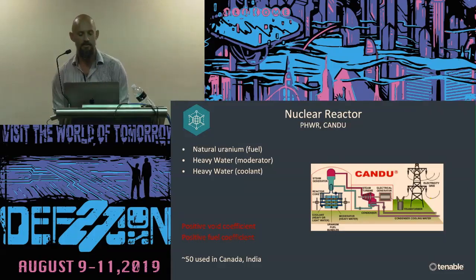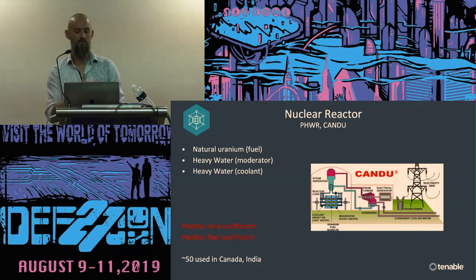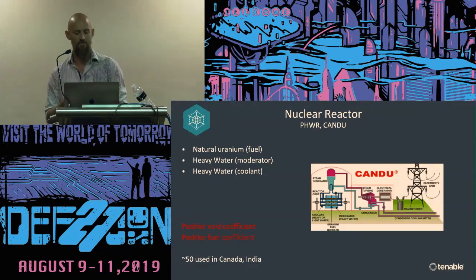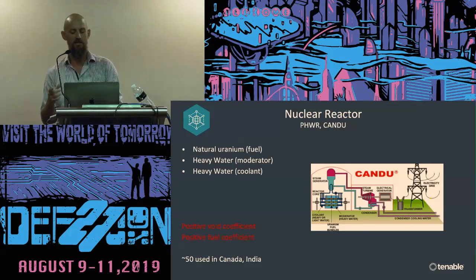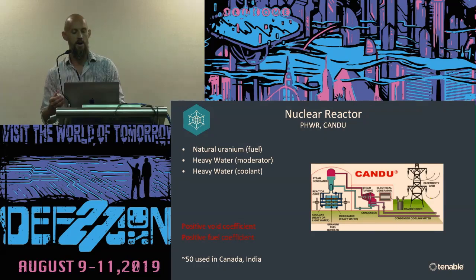A third type is the pressurized heavy water reactor — called the CANDU, mostly used in Canada. It's a modification of the PWR but instead of light water, it uses heavy water — deuterium, which is another hydrogen isotope. Deuterium already has the extra neutron that light hydrogen would have absorbed, so there's reduced neutron absorption, making it easier to sustain the chain reaction. That means they can use unenriched or lower-concentration uranium as fuel, which is cheaper. However, the design is much less stable, with circumstances where reactivity can increase as the water starts to boil.